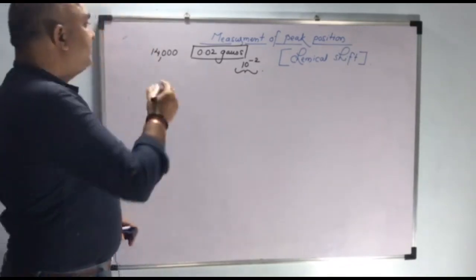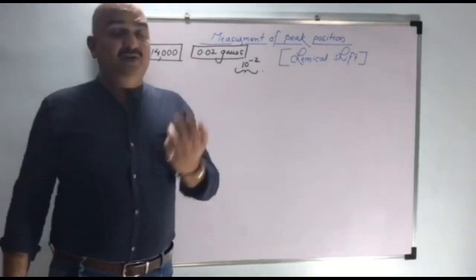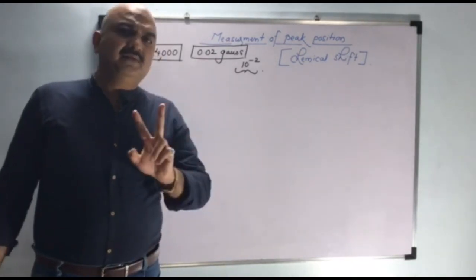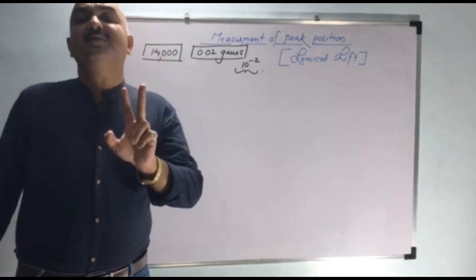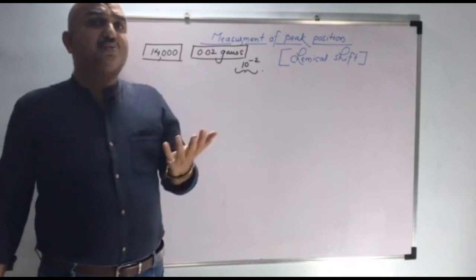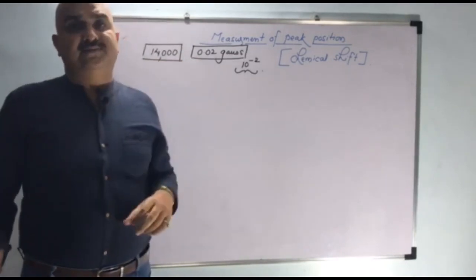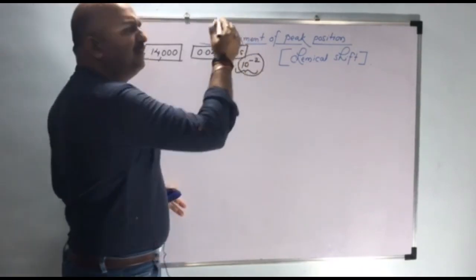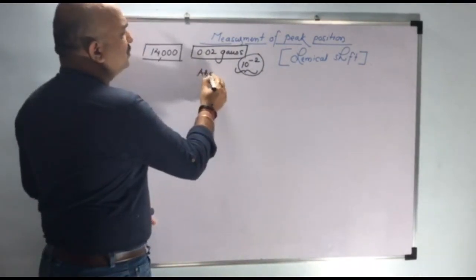Our instrument is producing a magnetic field of around 14,000 Gauss. Please see the difference. H1 NMR spectroscopy gives different signals, but sometimes the difference in magnetic field between two peaks is only 0.02 Gauss while our instrument produces 14,000 Gauss. So it is very difficult to measure this factor of magnetic field and very difficult to measure the absolute peak position.